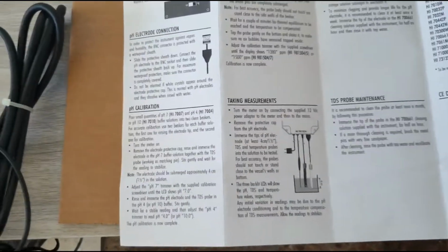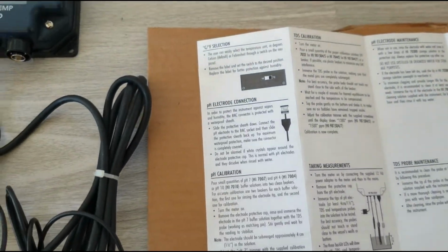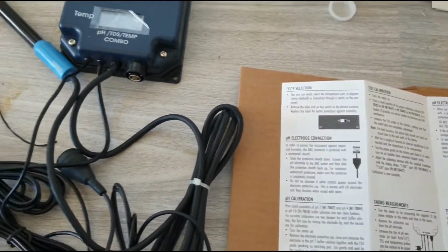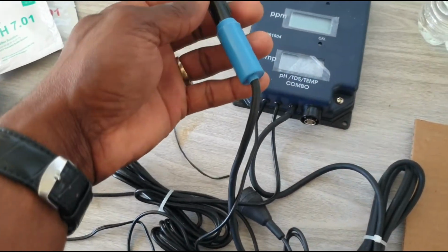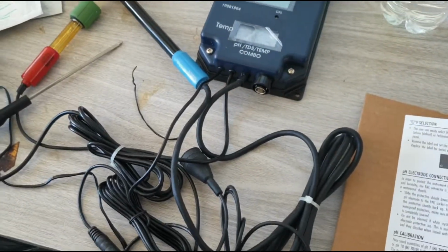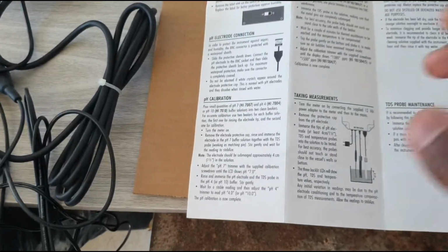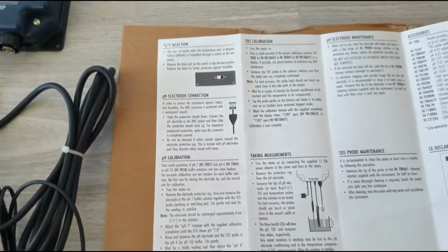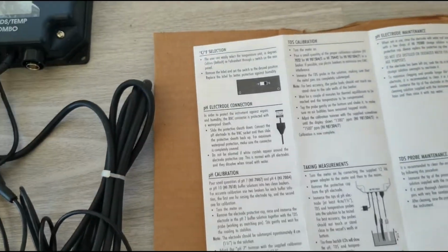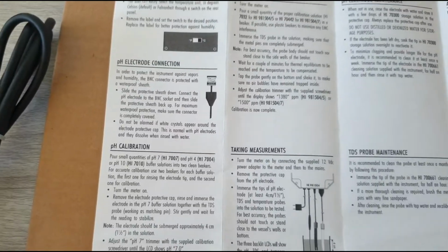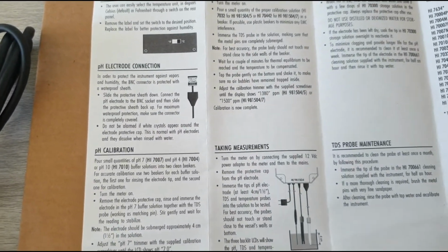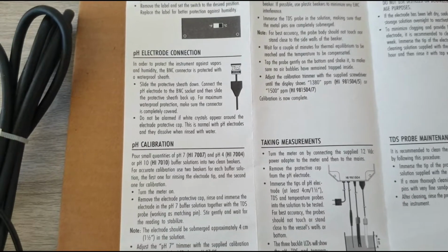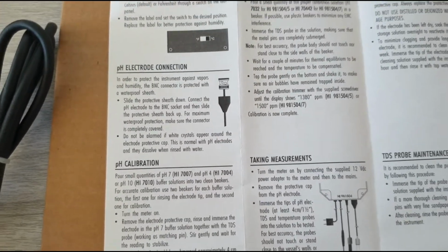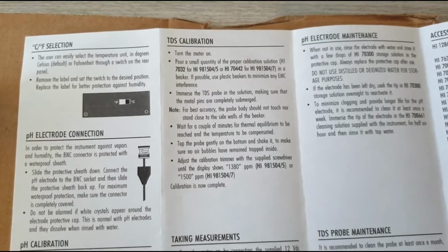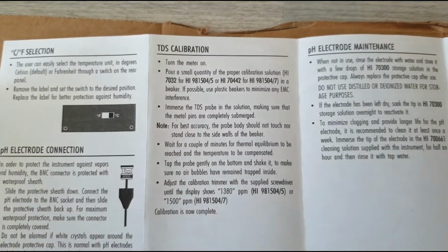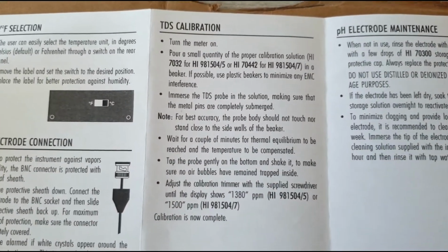This is the manual. So first you're basically going to calibrate pH 7 and then pH 4, and after that you calibrate the ppm probe. Now let us look for the calibration instruction for the ppm, because different meters will give you different conversion figures, or different calibration figures. So let us look at this one. The TDS calibration, right?